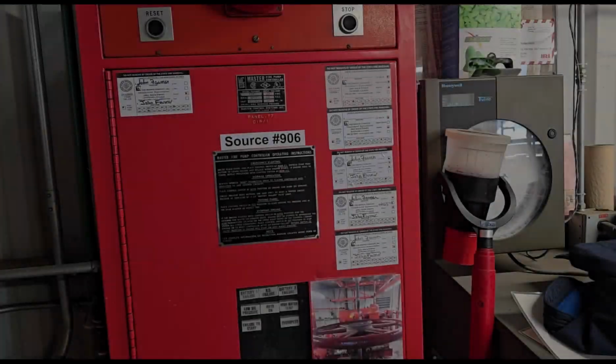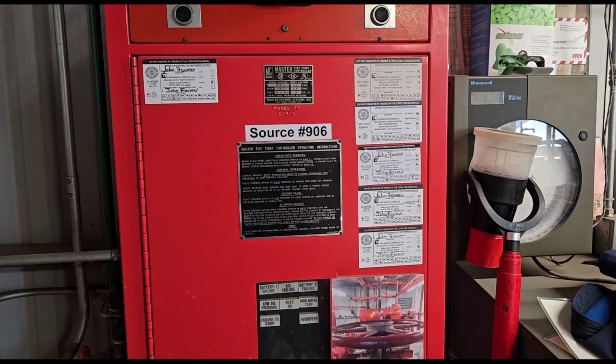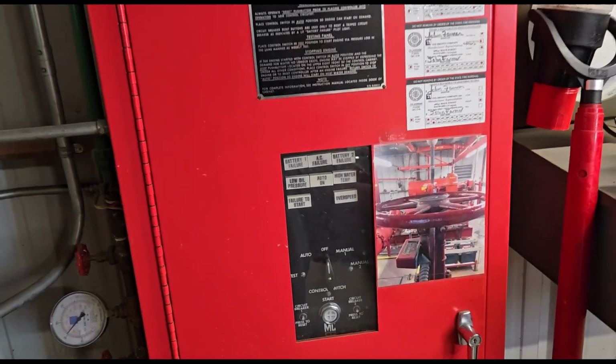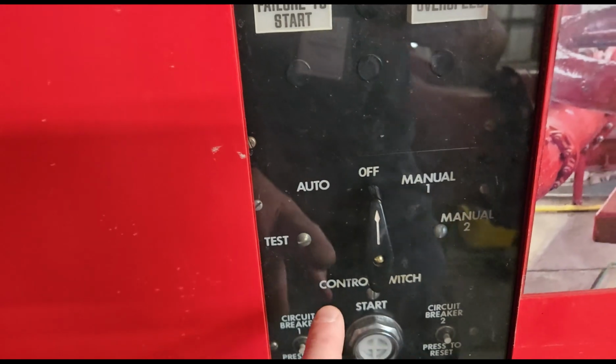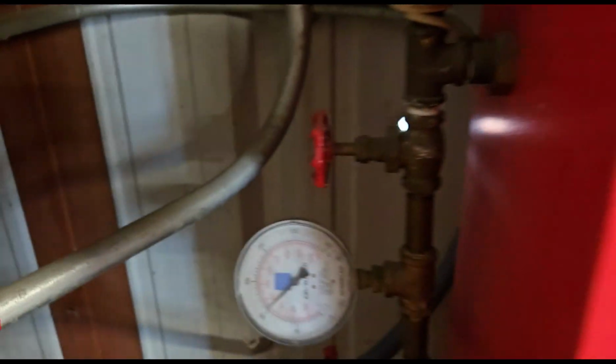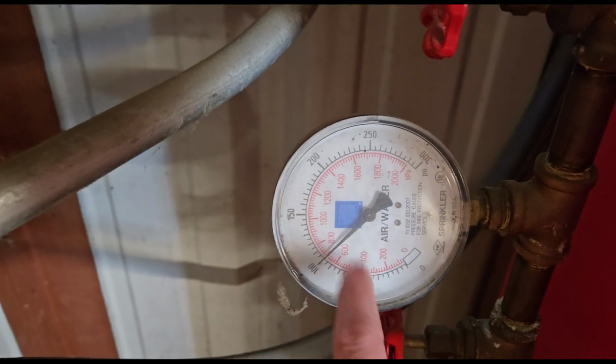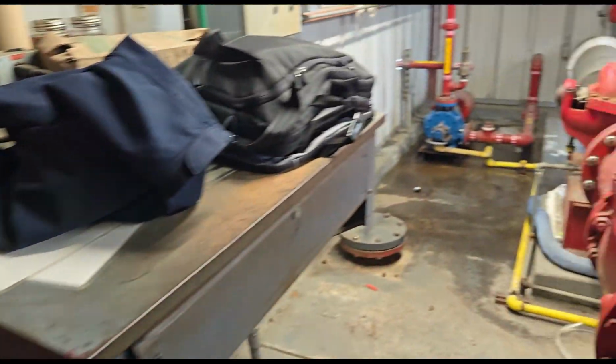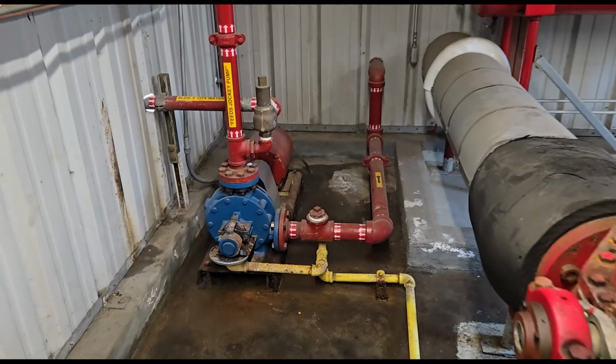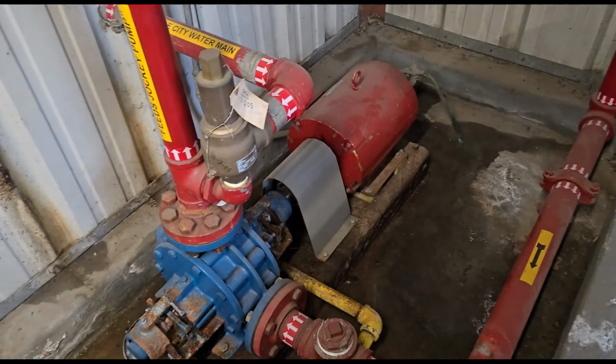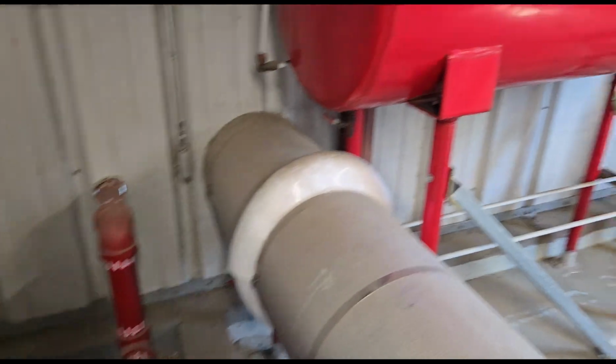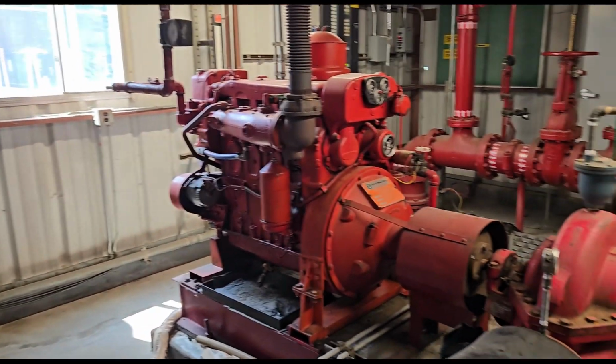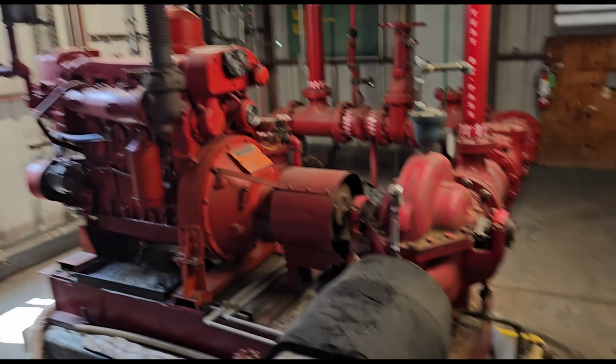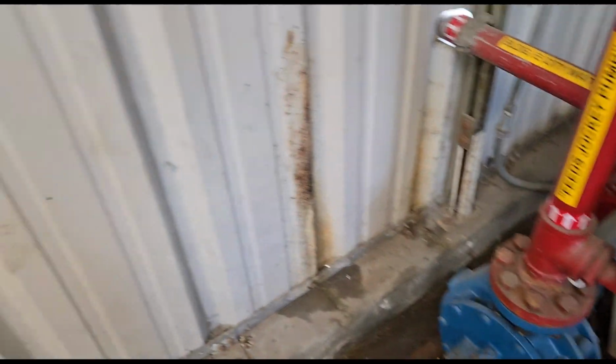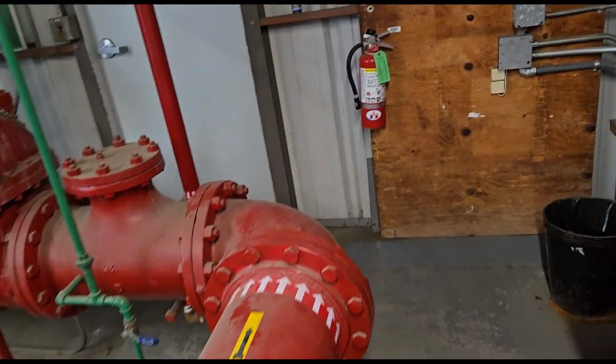All right. So now we have finished our flow testing. We're back at the fire pump, still in off. And the PSI is back to 100, just to make sure our jockey pump is turned off, so it's done pressurizing the system. And of course, as long as the fire controller's off, this guy's not turned on. Otherwise, it would be very loud in here. So this guy's turned off. We got our pressure back up.